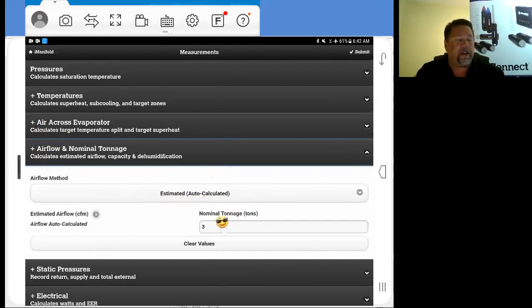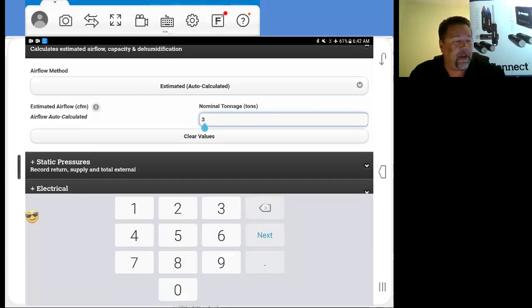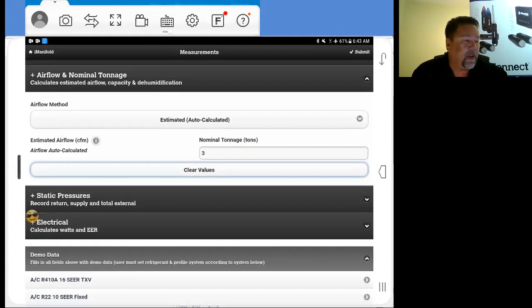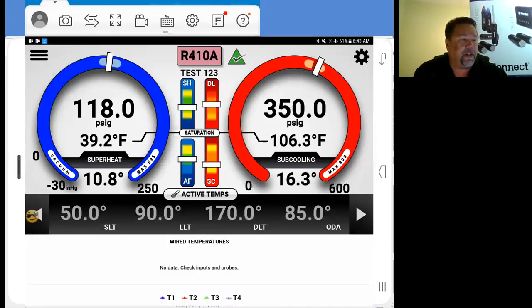And you can see our nominal tonnage. Now when I put in that profile, it puts in 3. If we had a 2.5 ton, we would enter 2.5. If it was a 3.5, 3.5. Just make sure that you do not put BTUs in there, because if it was a 3-ton nominal system, like it is here, you put in the 3 and hit submit. If you put in BTUs, 36,000, it's going to look for 36,000 BTUs of airflow, which we don't have. So now we have our tonnage in there. Tap submit. Our tonnage is in there.